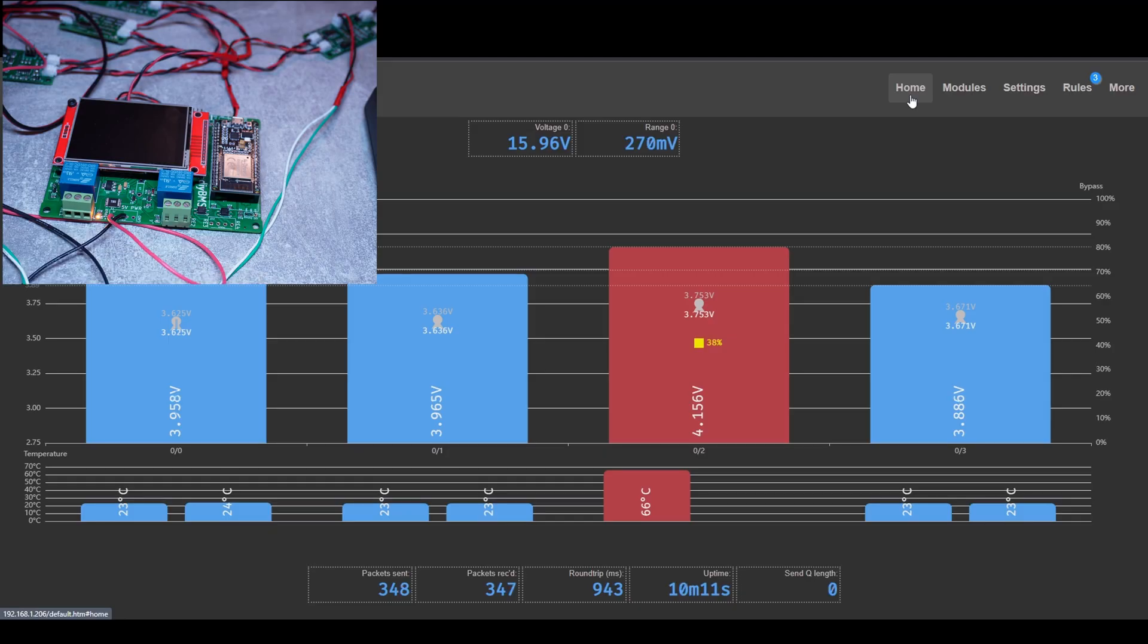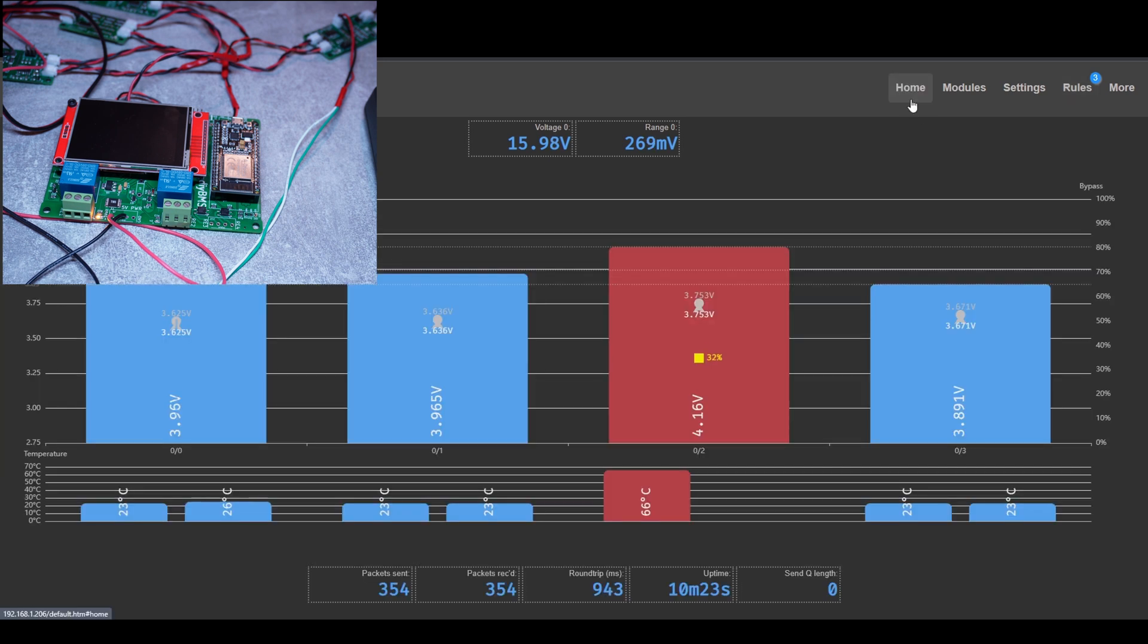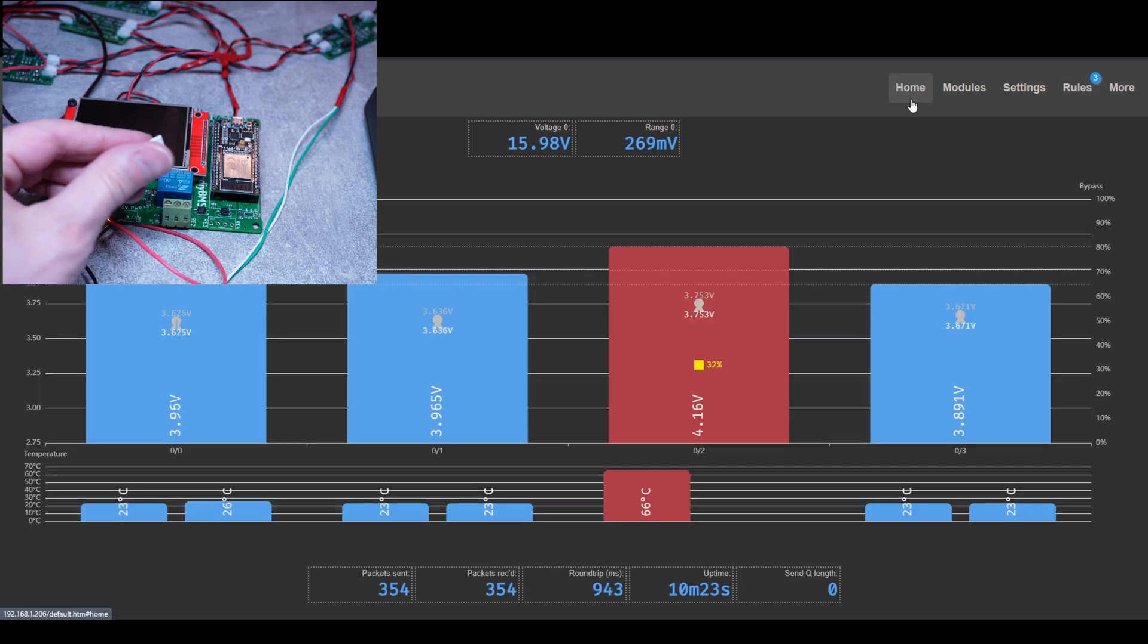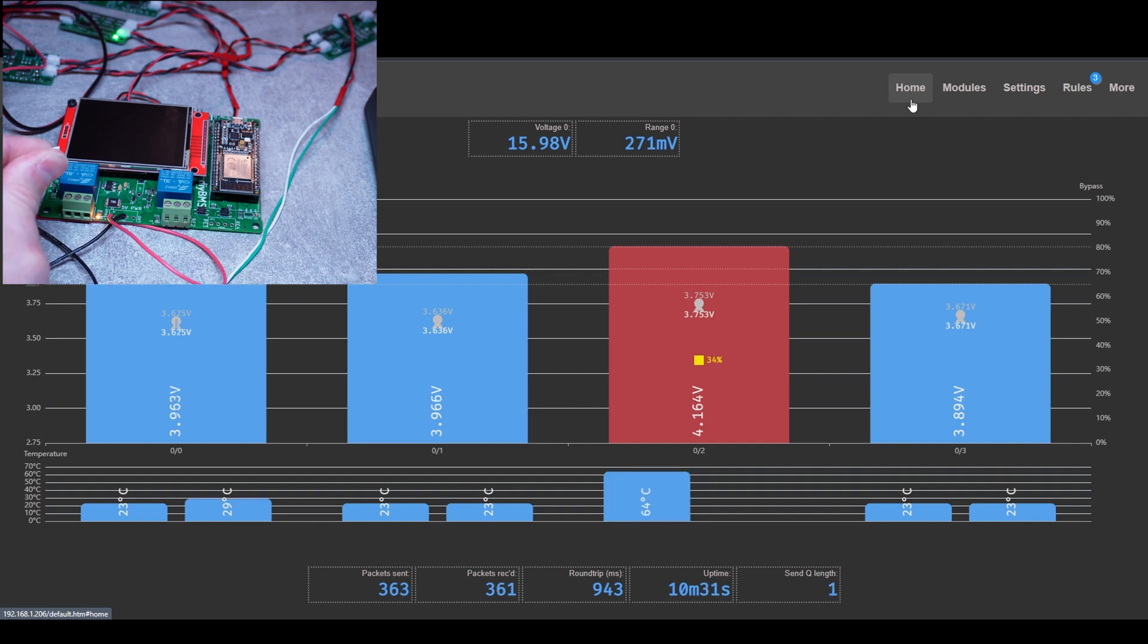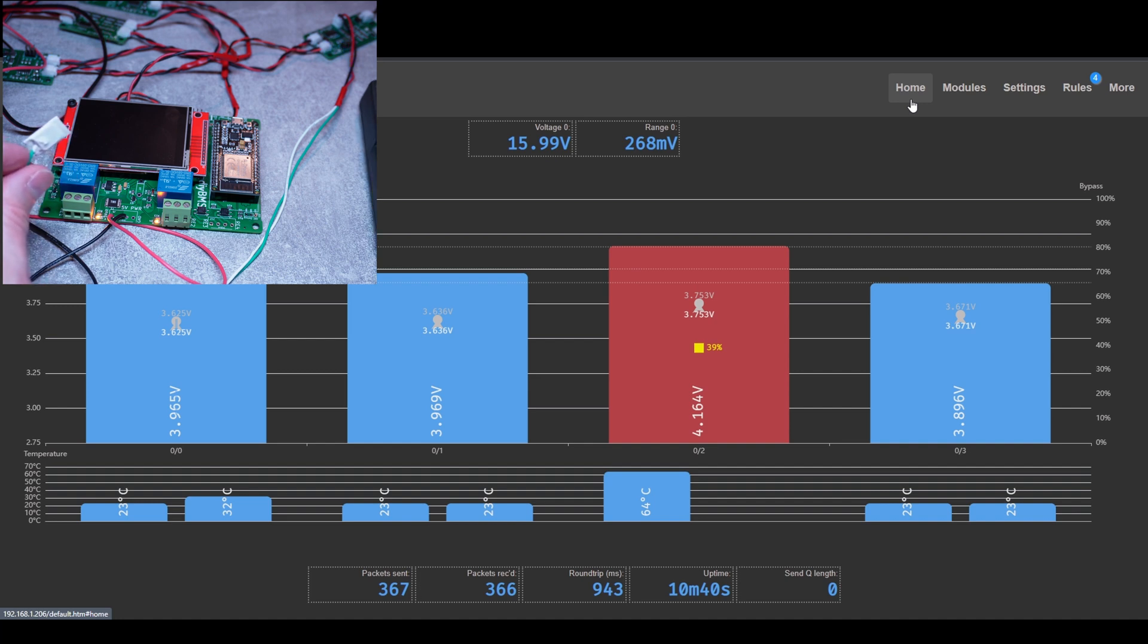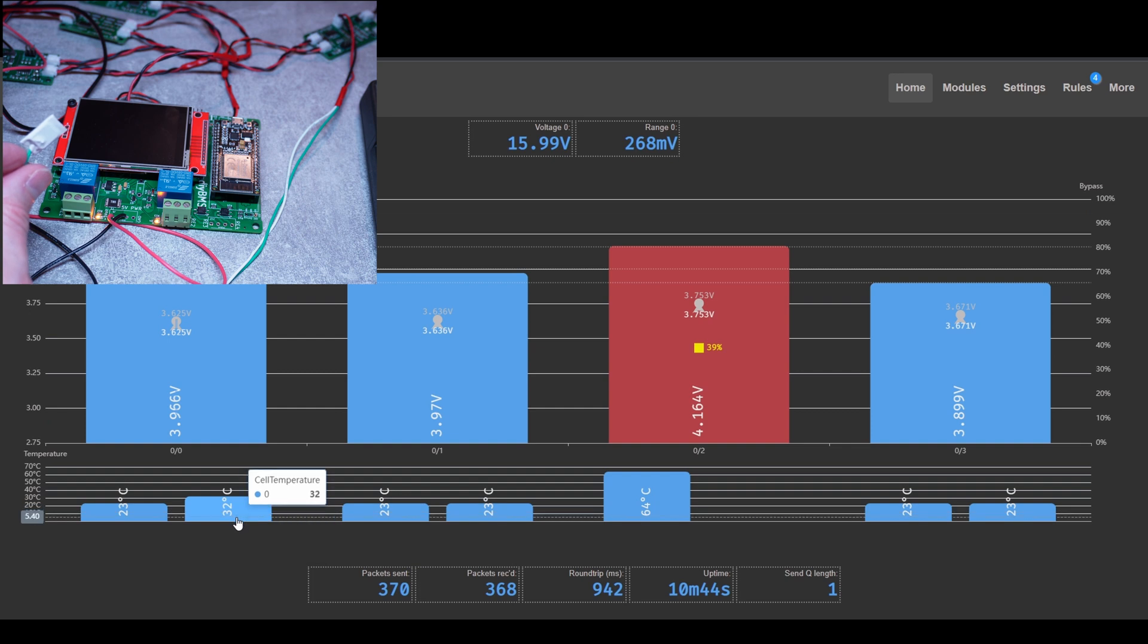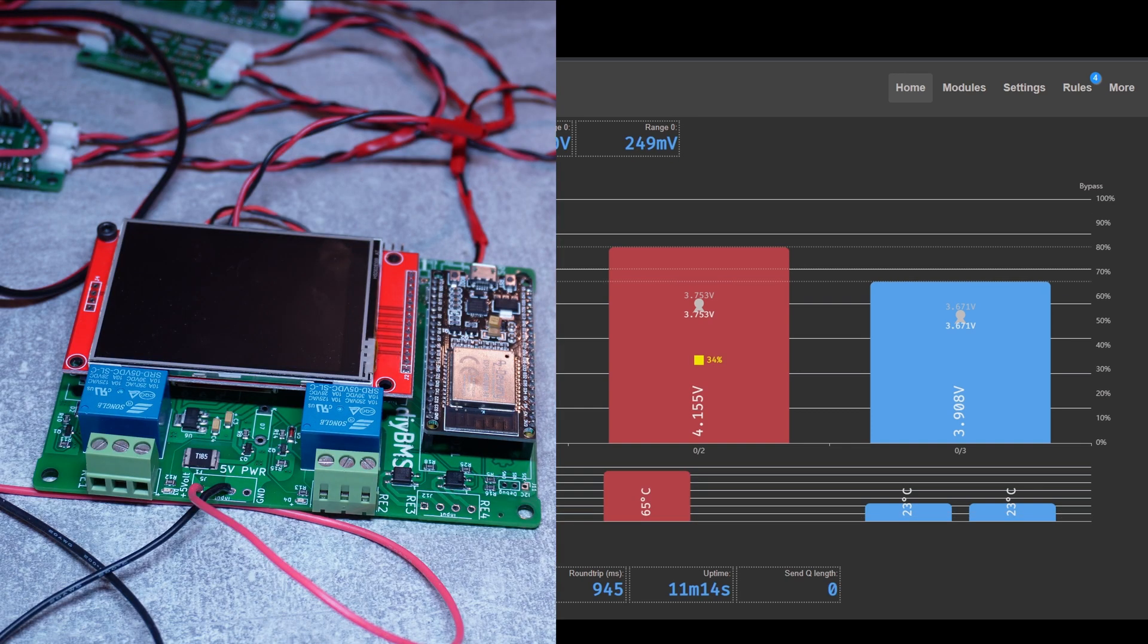The other relay has rules set up for cell temperature above 30. So if I now hold my hand over the external temperature sensor, we hopefully will have this second relay come on. Yep, you can see it has come on. Now if I release my hand, it's hopefully gonna cool down. So now we see 32 when it goes below 30. 29, yeah. And we can see the relay has gone off.